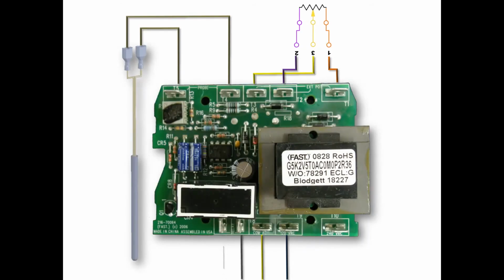Here at the board we see T6 missing, which also prevents T7 output from the relay. The potentiometer, probe, temperature control board, door switch, fan centrifugal switch, heat cutoff switch, CR1 relay, and the transformer make up the first half of the heating circuit.